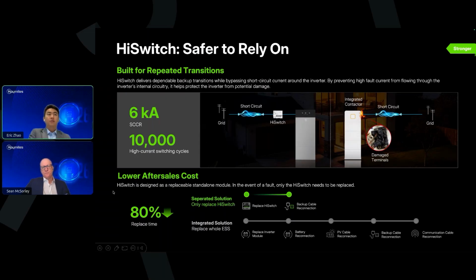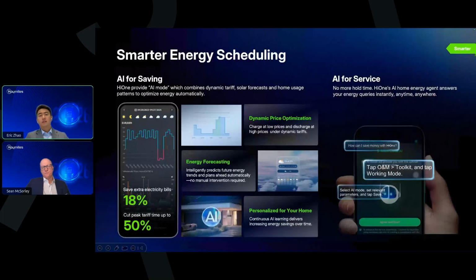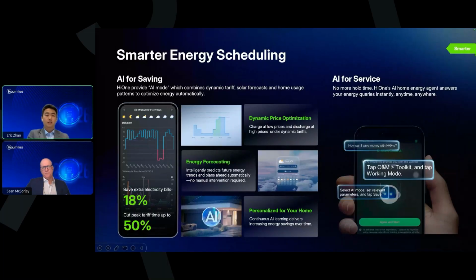Exactly. That's why we introduced AI functionality into the residential energy storage system. Backup is important when the grid goes down, but most days the grid works normally, so the system also needs to create value for the homeowner every day. HiOne provides the AI mode for smart energy scheduling. As shown on the left-hand side, the AI mode combines information such as dynamic electricity tariff, solar generation forecasts, and household energy usage patterns. Based on these inputs, the system can optimize charging and discharging behavior automatically.